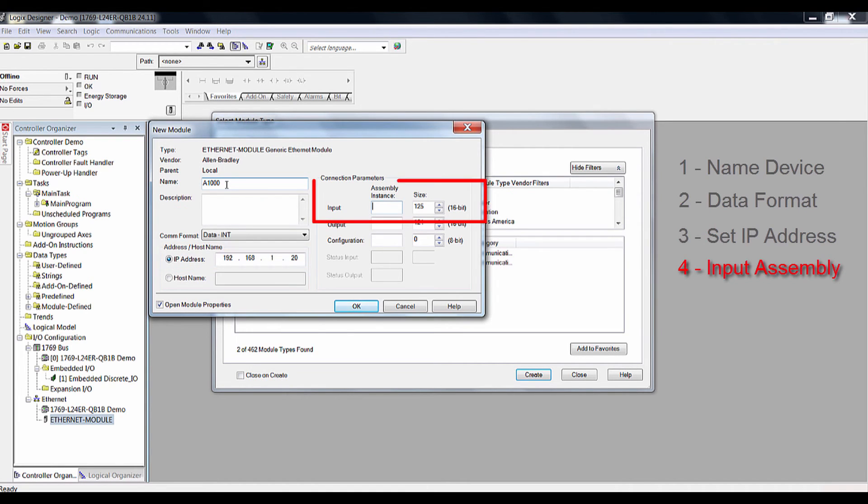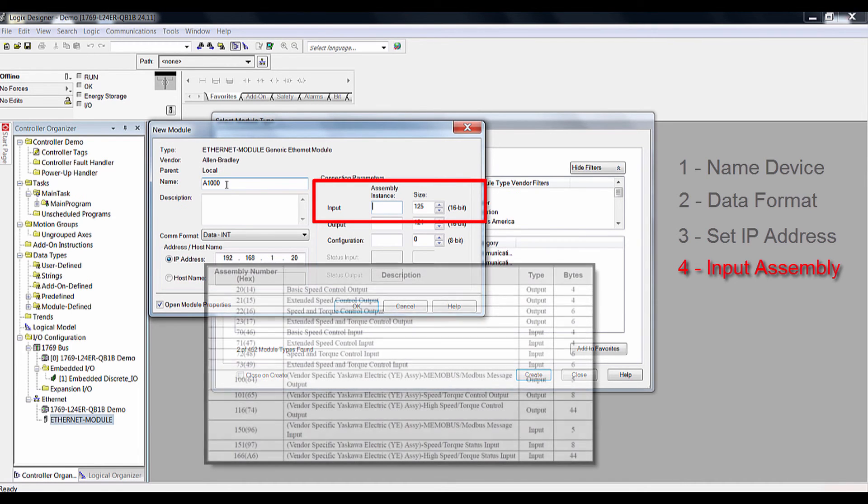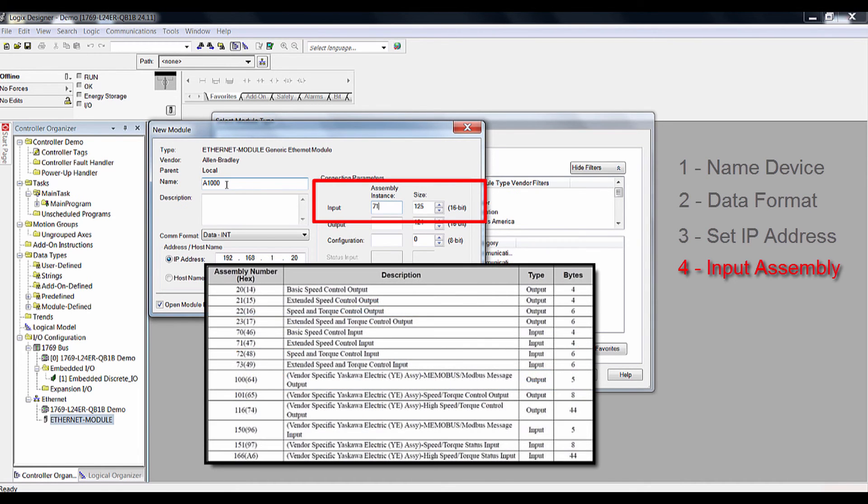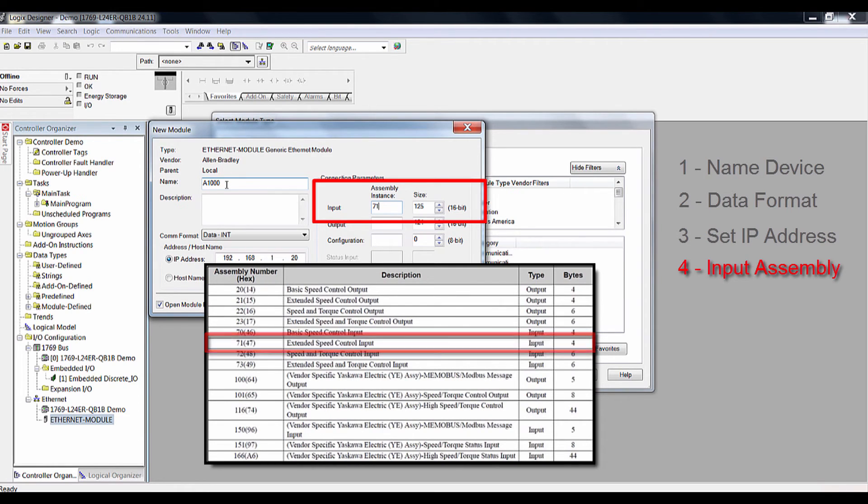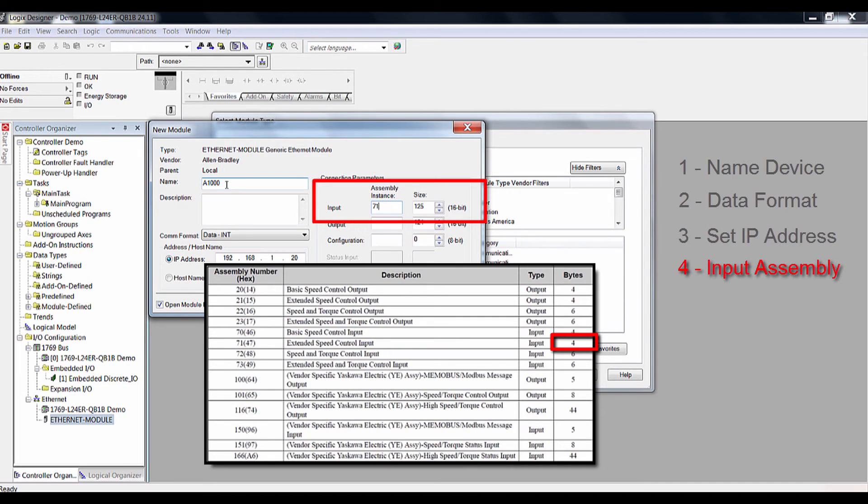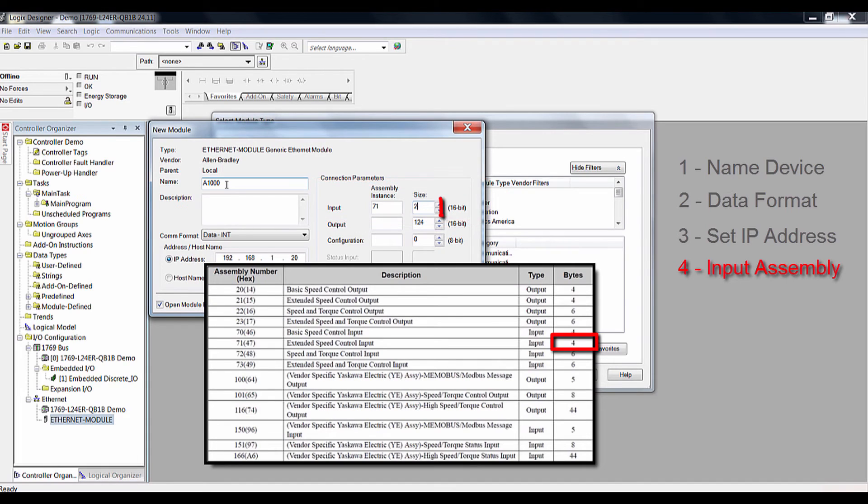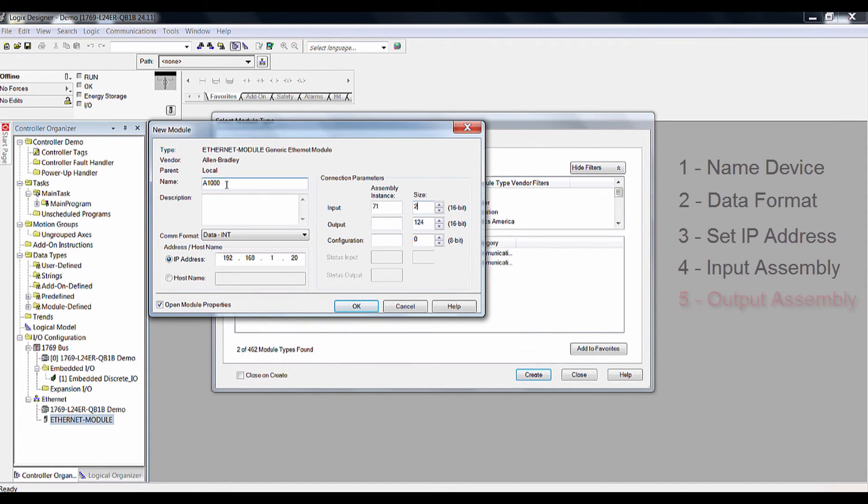Four, change the input assembly to your desired assembly. Please refer to the Ethernet IP manual for a list of available assemblies. For this demonstration, we are going to use assembly 71, which is a 4-byte or 2-word assembly. We'll change the size of the assembly to 2, since the size adjustment is in terms of a 16-bit word and not an 8-bit byte.